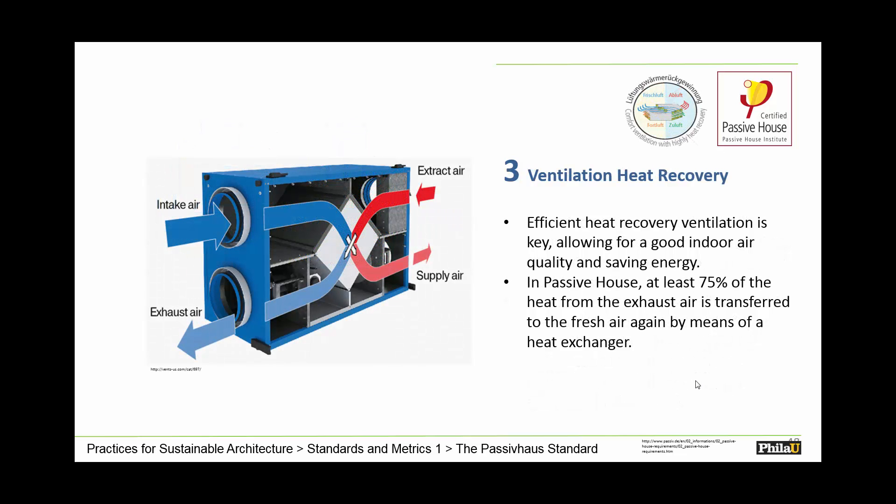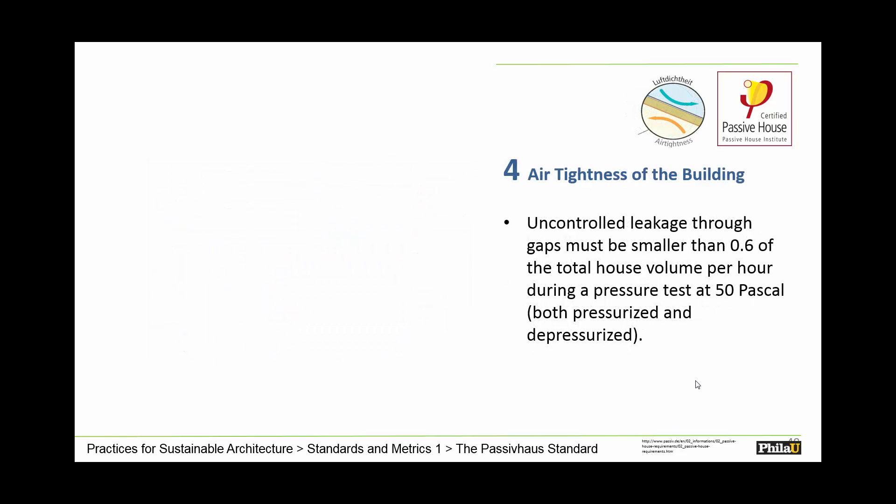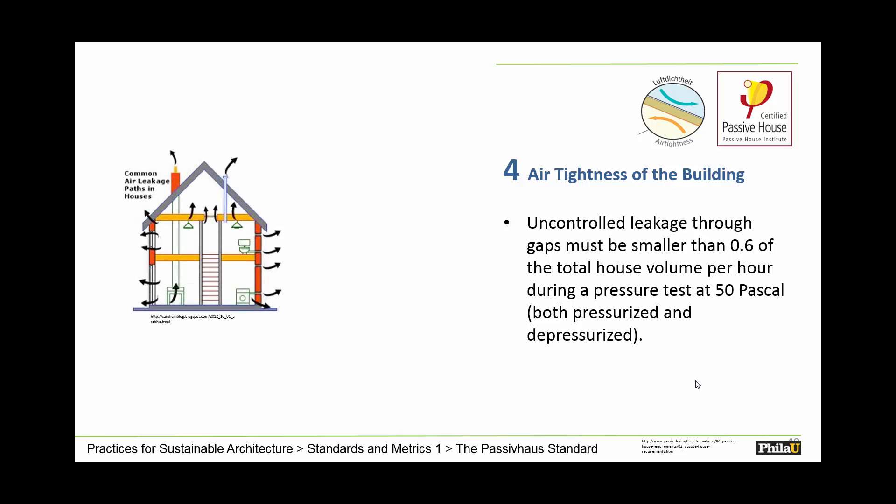Ventilation heat recovery units are critical to the success of passive house. With enough air moving through the building, we take advantage of the fact that warm air can be reused — that temperature in the warm air can be recaptured to warm incoming air again. The airtightness of the building requires that uncontrolled leakage gaps be smaller than 0.6 air changes per hour. Constructors must think very carefully about the quality of the envelope. You would never have a fireplace in a passive house — the idea is to seal it as tightly as possible, just like pulling a blanket over your head, creating a continuous, unbroken airtight barrier.